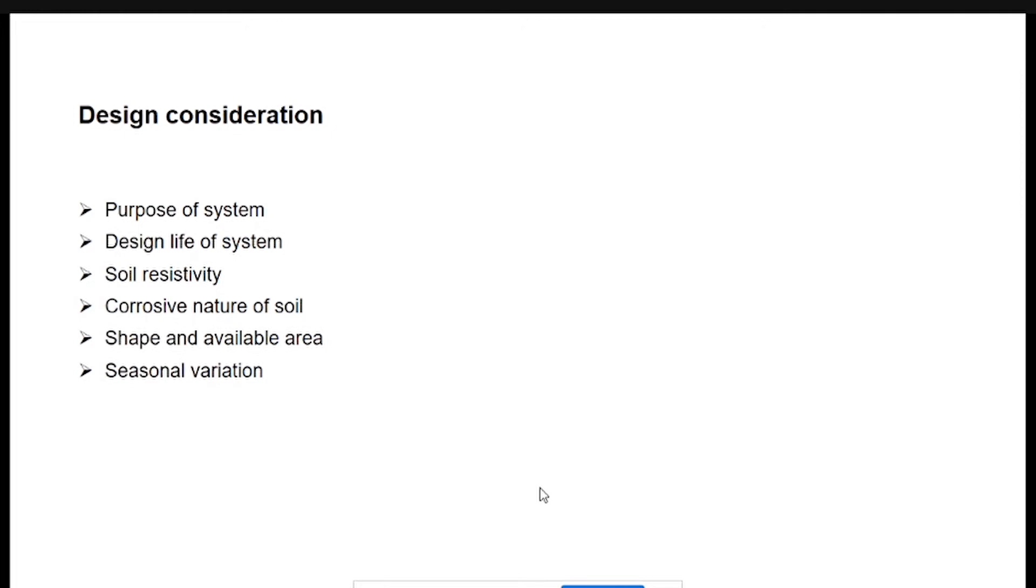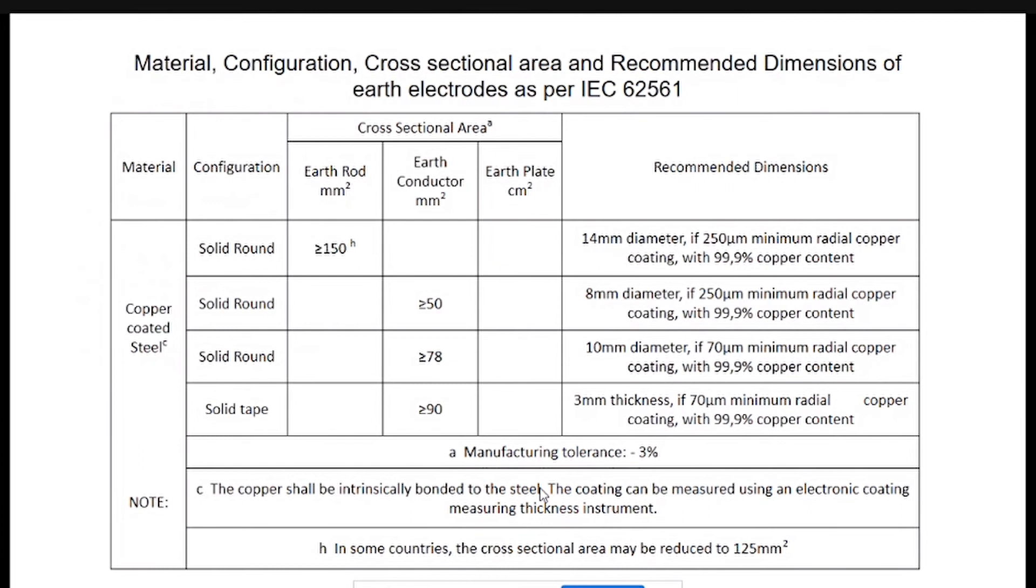The corrosive nature of the soil is important because it determines the material you need to provide for earthing. Very importantly, shape and available area matter because many times we design only with AutoCAD drawings without a clear picture of what's at the site. A practical study of site is important because with AutoCAD you can design 100 earthing systems, but practically there may not be sufficient space to implement them.